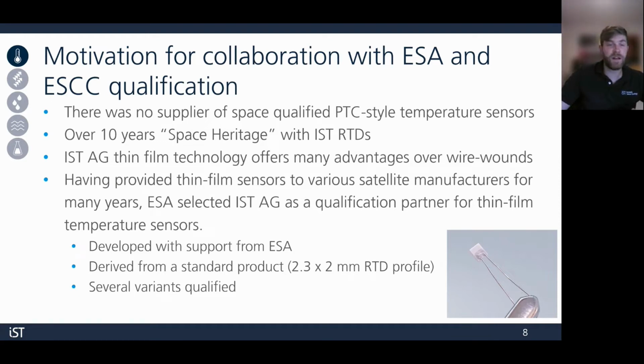The thin film platinum technology offers several advantages and could be implemented well in many space and other high reliability applications. So having supplied thin film sensors over years for various satellite manufacturers, ESA selected IST AG as a partner for the qualification of thin film platinum RTDs. Over 4 years with the support of ESA, we achieved ESCC qualification for 10 different temperature variants, 10 different sensor variants covering 2 temperature ranges and 5 nominal resistances.